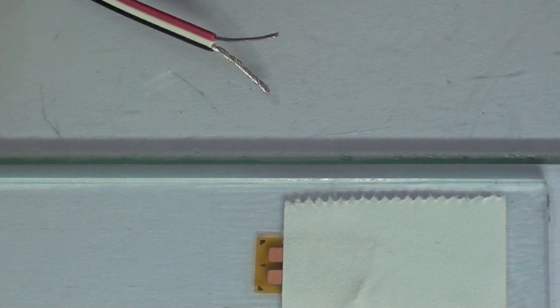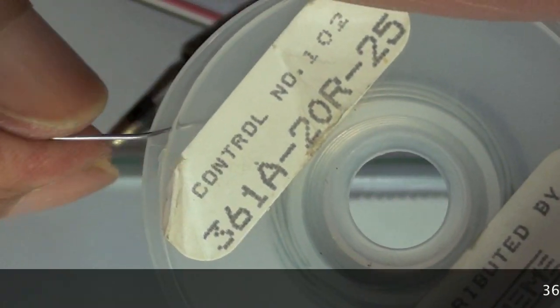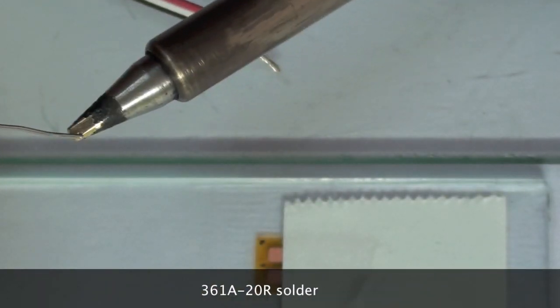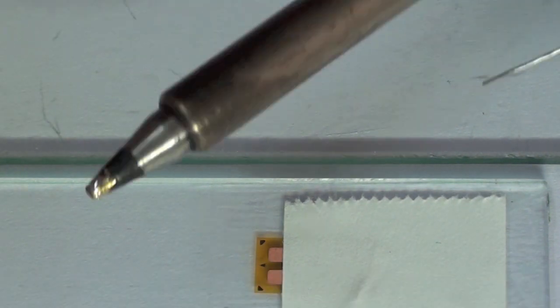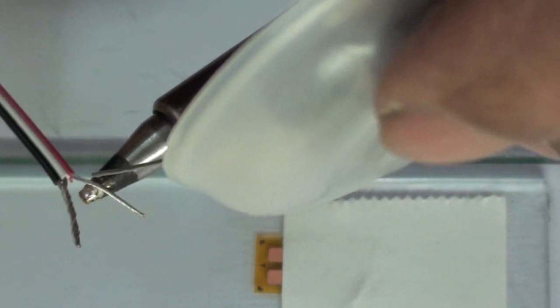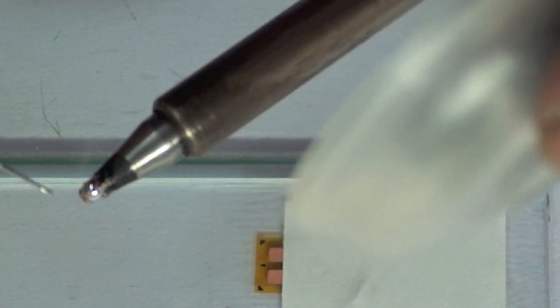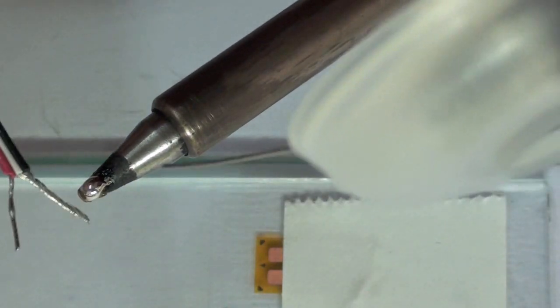The conductors are then tinned with 361A-20R solder which has a lower melting point than most other solders. Fresh solder is applied to the tip of the soldering pencil to make a pool. The edge of the conductor is placed in the pool of solder, then fresh solder is fed into the pool as the lead wire is drawn away. This process is repeated for the other bundle of conductors.